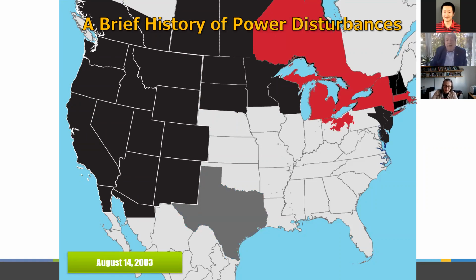The big one, I was on the blackout investigation team for this at NERC. Pretty straightforward: two trees and two computer failures was the root cause of this outage. The computer failures were fairly serious. The SCADA coming into Akron was frozen, and data was coming in but it wasn't correct. In Indianapolis, the state estimator had inadvertently been turned off, so they were flying blind. This took a long time, more than an hour to propagate, and we had a lot of swings within islands. Fermi nuclear plant dropped to 49 hertz and was still trying to run when the reactor feed pumps tripped. So there was some damage to equipment, longer term, not necessarily instantaneous damage.